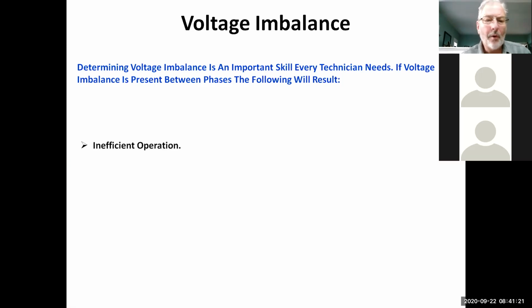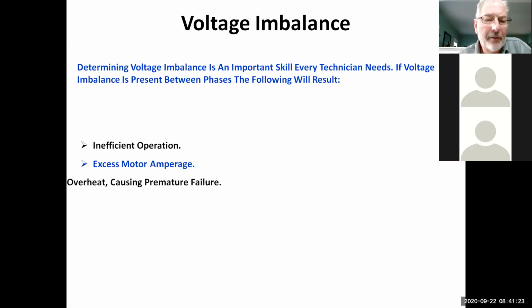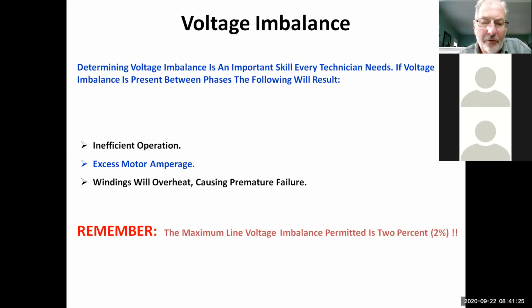One of the things I want to talk about is voltage imbalance. It's important on the system. When you're running these systems, if you do a startup, make sure you check the voltage, check the amp draw. It leads to inefficient operation, overheating, failed compressors. It can cause you all kinds of problems, and for the little bit it takes you to do it, it's something that's very, very important.